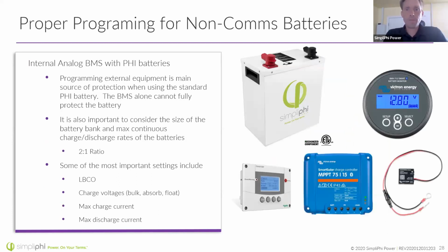So internal analog BMS units, the big difference is that they don't have communications. They're not easily controlled, and so there are still very advanced BMS units that go into our PHI batteries. But these units don't offer closed loop communications and don't offer individual information about different batteries. There's still a good place for these. A lot of people love the PHI batteries because you can use external equipment to provide many of these abilities with batteries. So with an analog BMS, with our PHI batteries, you can use external equipment.